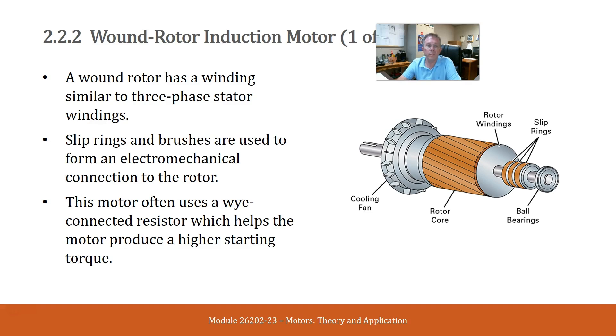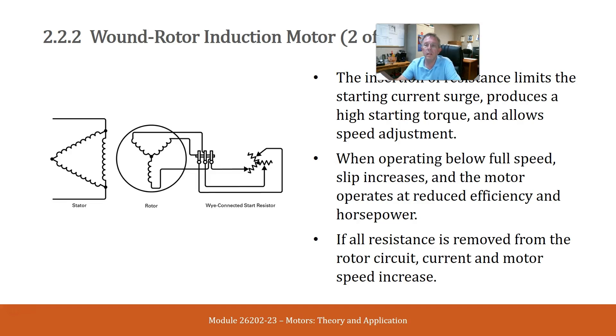Wound rotor induction motor. A wound rotor induction motor has a winding similar to a three-phase stator winding. Slip rings and brushes are used to form an electromechanical connection to the rotor. This motor is often used with a Y-connection resistor which helps the motor produce a higher starting torque. The insertion of resistance limits the starting current surge, produces a high starting torque, and allows speed adjustment. When operating below full speed, slip increases and the motor operates at reduced efficiency and horsepower.